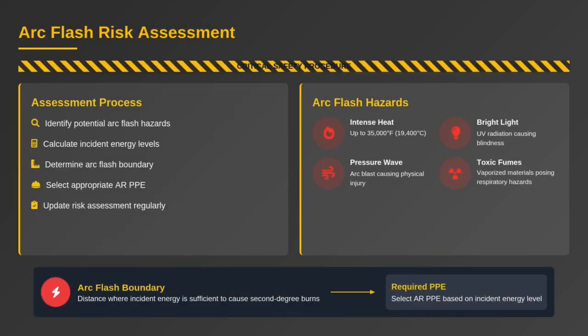Arc flash risk assessment determines how much energy could be released during an arc event. This process identifies potential hazards, calculates incident energy, defines the arc flash boundary, and selects proper arc-rated PPE. Remember, the goal is to keep workers outside the boundary where second-degree burns could occur. Assessments must be updated regularly to reflect changes in equipment or conditions.